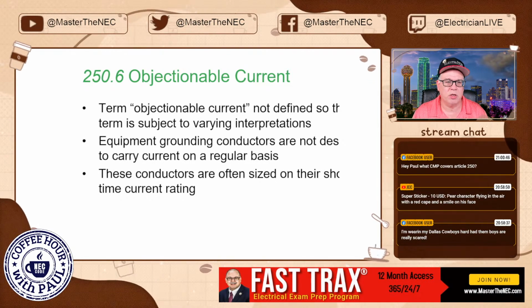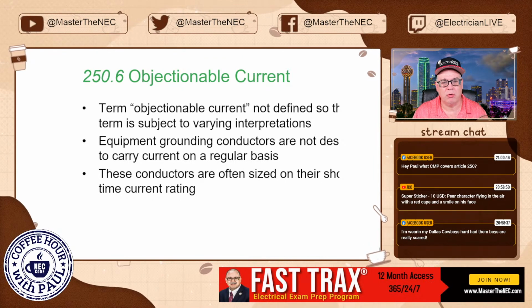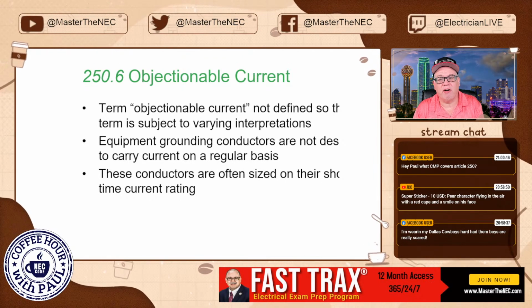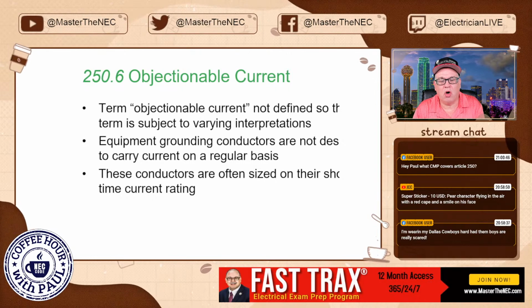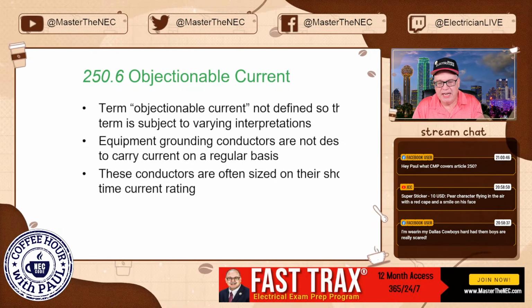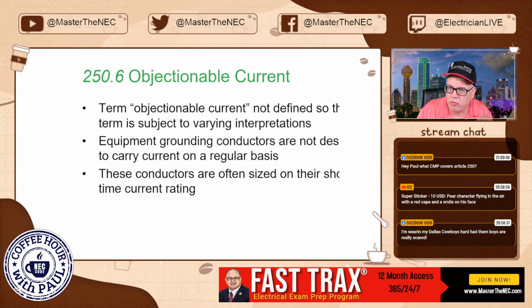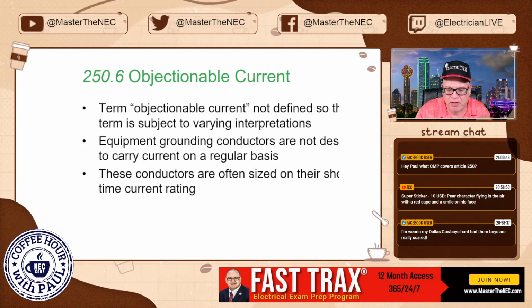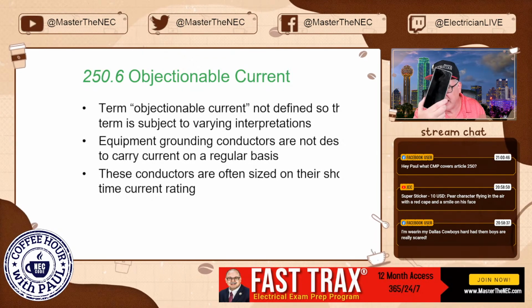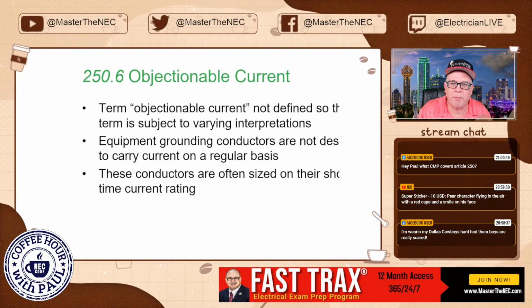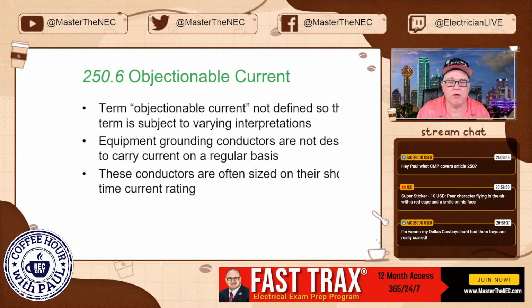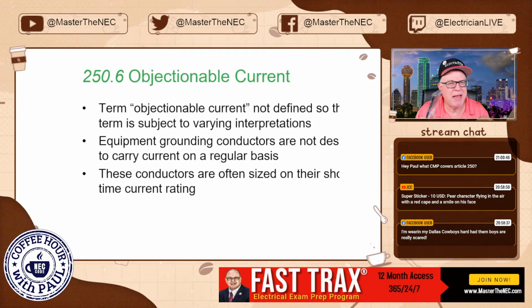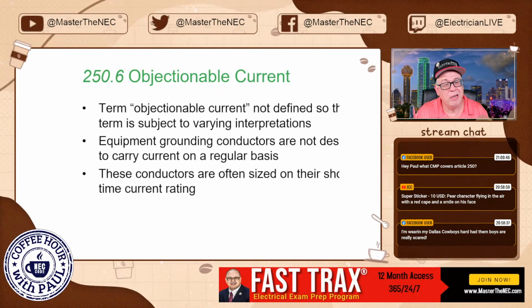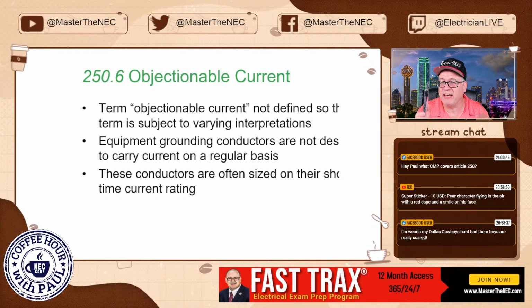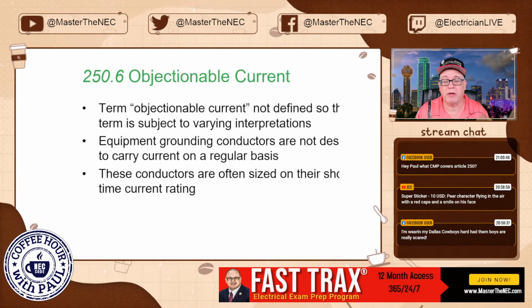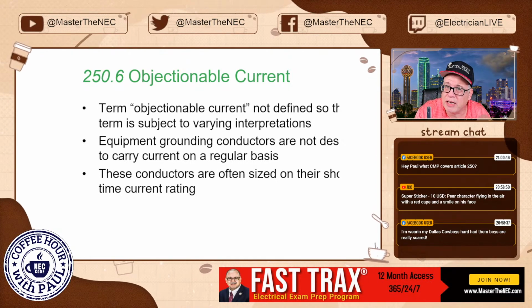What is objectionable current? Equipment grounding conductors are not designed to carry current on a regular basis. So if you were to do an improper case to neutral, let's just say that picture I showed you on Trade Hounds, where the main bonding jumper was installed downstream of the service, now it's not a main bonding jumper anymore. It is a jumper, but it's improperly installed. So now the grounded conductor, or the neutral in that case, is making a connection to the enclosure.